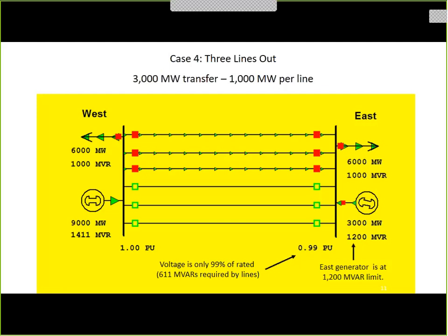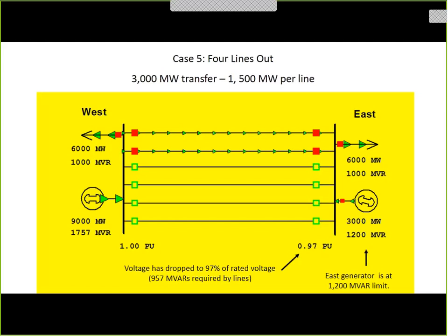Now, over there on the west side, there is no limit. We call that an infinite bus. It can put out as many as you want. Take out 4 lines. Now we're getting pretty serious. The transfer is now 1,500 megawatts per line. There's only 2 left. We're still at a VAR limit here. Voltage is going down. It's 0.97. But that's only 3%. That's not bad. The West is an infinite bus, so it keeps producing extra VARs to make up for the losses.